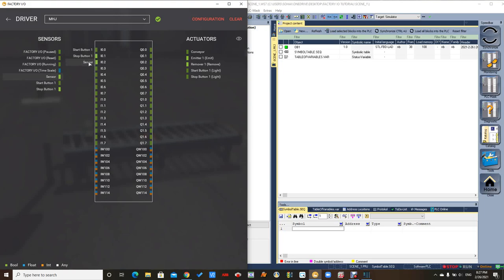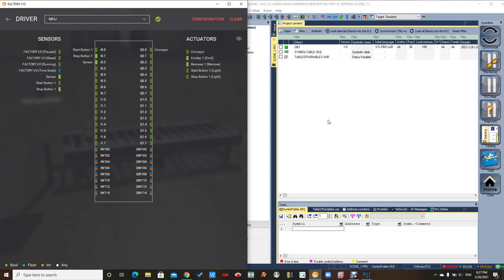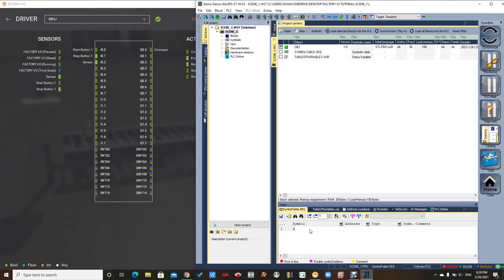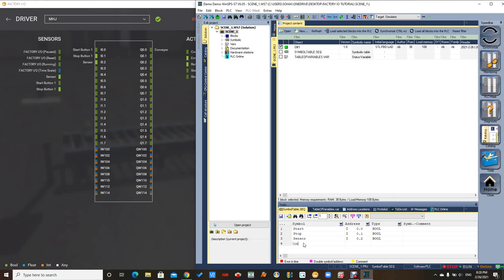In the drivers I have the inputs or sensors and actuators or outputs. First, I'm going to put the start button on I0.0 and stop button on I0.1 and the sensors for counting how many boxes pass the conveyor. And here is the conveyor. I'm going to name all the inputs and outputs: start I0.0, stop I0.1, sensor I0.2, and the conveyor Q0.0.